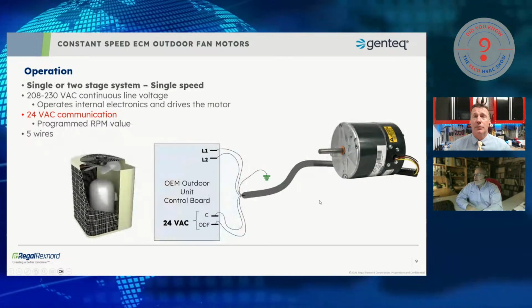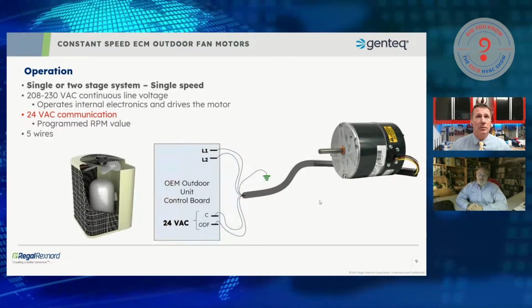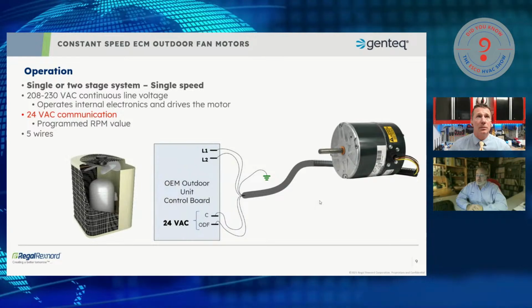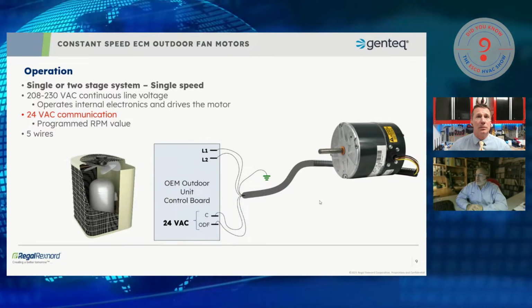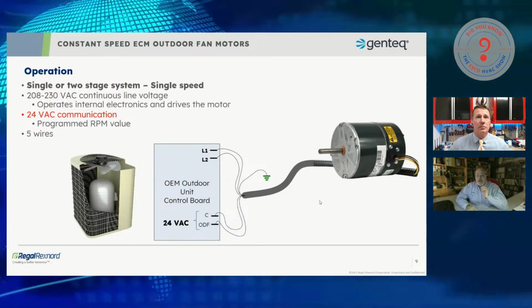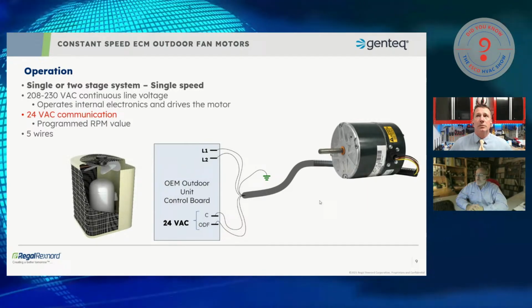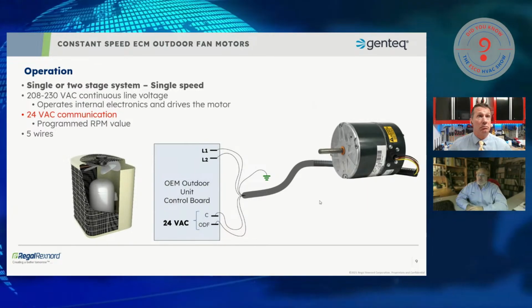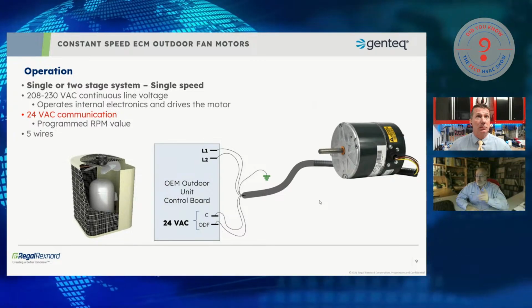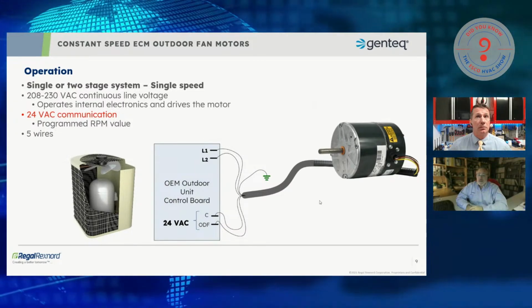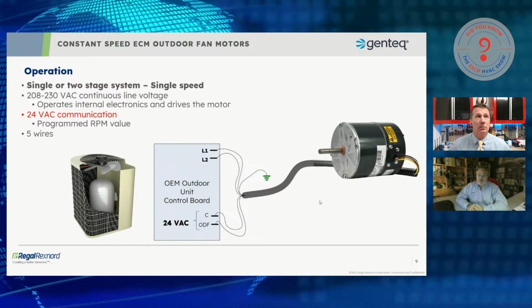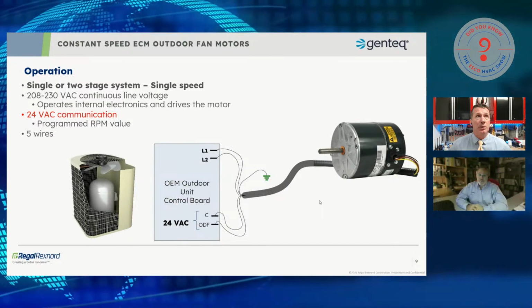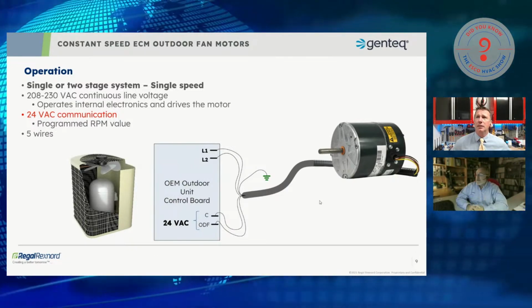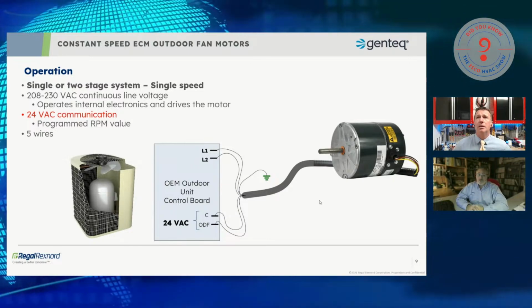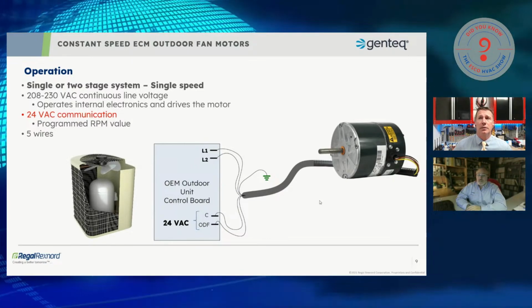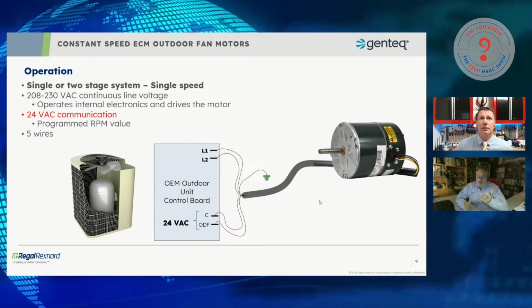Indeed. So there are quite a few manufacturers. I was surprised as I started learning more about our outdoor fan motors and teaching them that there's quite a few manufacturers that use the ECM motor just at a single speed. And so in this case, where there's only 5 wires going to the motor, a line 1, line 2, ground, common, that's 4, and then your speed wire. Basically this motor spends its whole life looking for 24 volts on that 1 wire and turning on at 1 speed. And when that 24 volts goes away, the motor shuts off. The line voltage is there continuously, common's connected continuously, ground's connected to ground.